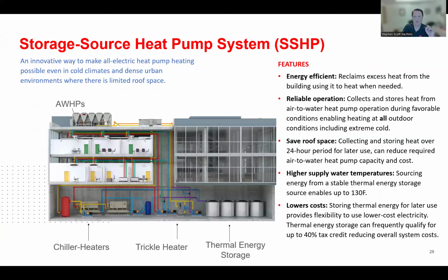Absolutely. And the efficiency is that the chiller heaters are taking the energy from the thermal storage batteries at, say, 0 degrees Celsius, which is a lot less work and much more efficient than if it had to be done solely by an air source heat pump. What it also does is enable the chiller heaters to operate at higher temperatures versus traditional heat pumps. You also get an energy benefit in this case because since you're heating with ice rather than at the lower temperatures, you do save energy on the building.